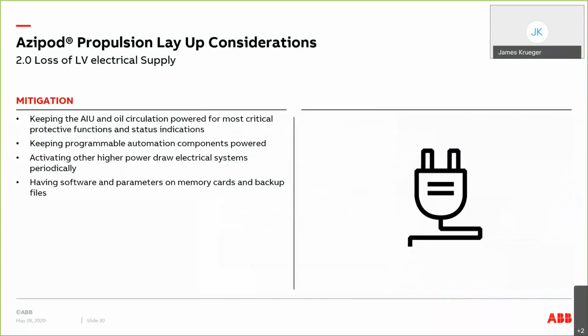Next slide. So as I said, the mitigation would be to make sure that we keep the LV power on for the AIU and the oil circulation, so that we keep the bearing oil healthy. We keep the programmable automation components powered up, so again, we don't run into the problems of losing software and whatnot. And lastly, we have to make sure that we have all software and parameters backed up just in case something were to happen and we do lose the LV power and lose backup systems such as UPS or even onboard RAM.